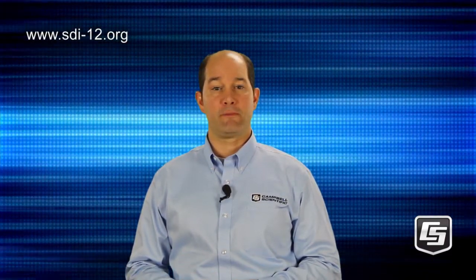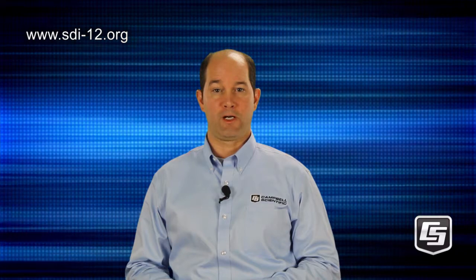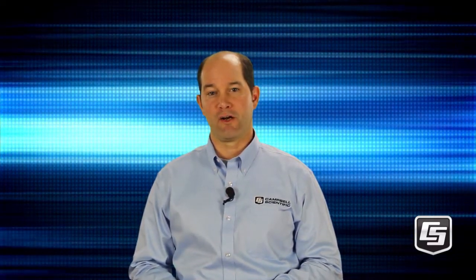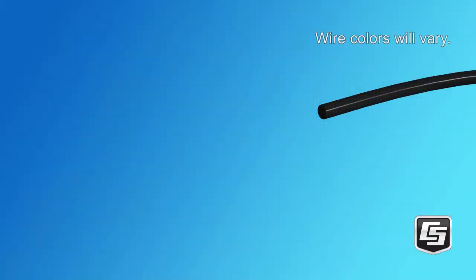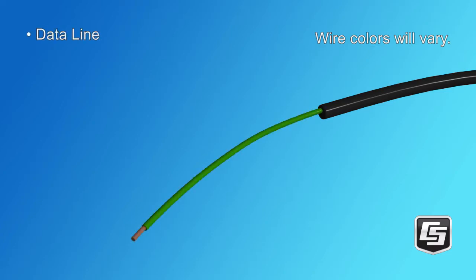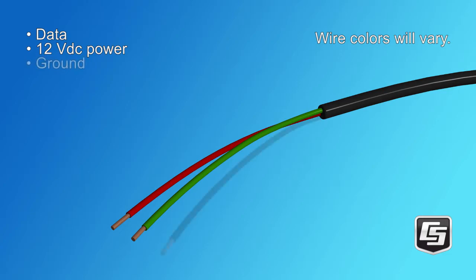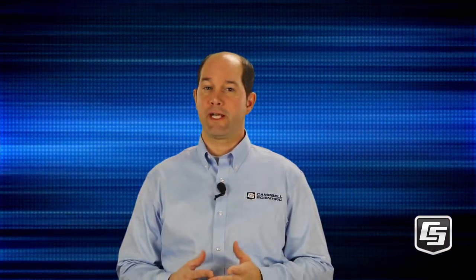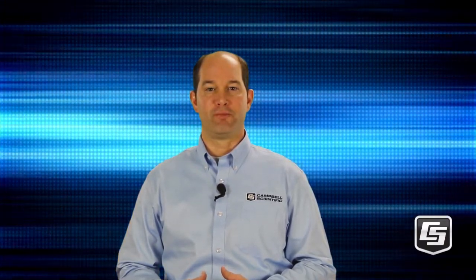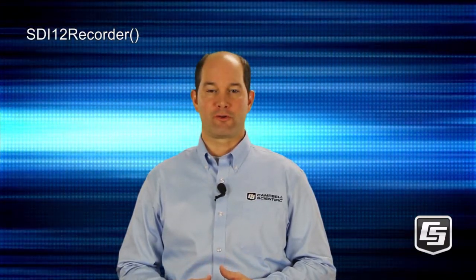SDI-12 stands for Serial Data Interface at 1200 baud. You can read the full specification at www.sdi-12.org. Some smart sensors can communicate with your Campbell Scientific datalogger using this SDI-12 protocol. All SDI-12 sensors have three wires: a data line that's used for transmitting and receiving information, a 12-volt DC power line, and a ground line. You can read more about programming your datalogger to read an SDI-12 sensor in the CRBasic Help. Take a look at the SDI-12 recorder instruction.